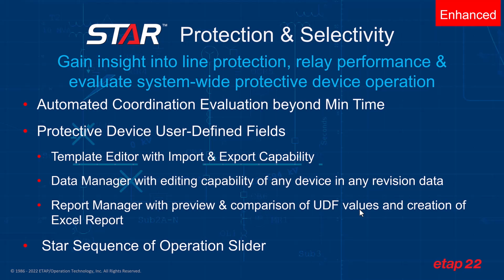And by doing so, you minimize the risk and you close the gap when you go from design into commissioning that particular device. By including functions within the device during the design phase that are not traditionally used in protection and selectivity, you are able to generate a complete report with a comparison of the user-defined fields, such that this report is given to the commissioning engineer and he can set up that device comprehensively from a single source of truth. This avoids any errors made during commissioning and any subsequent unforeseen or forced outages that were created due to gaps between what was done during design and what was implemented during commissioning.